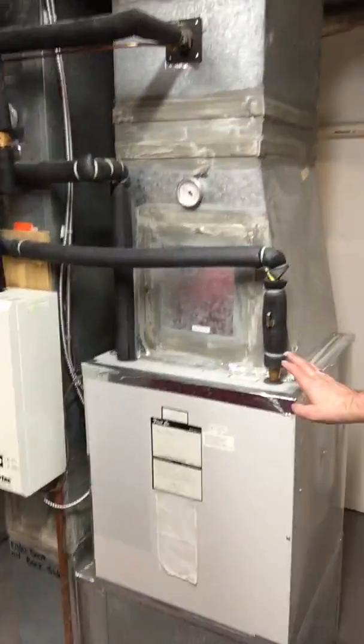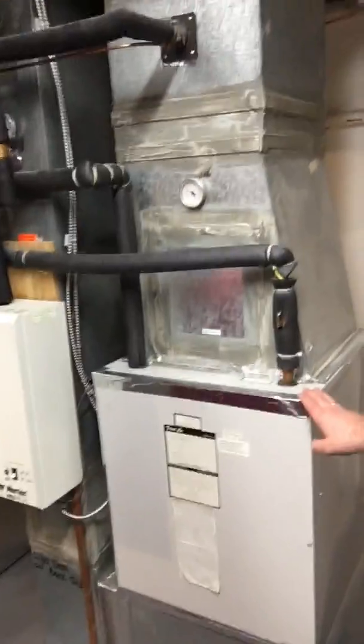So all right, so far we've talked about the snow melt, the pool heating, the radiant, the brains, the control system for that. So now I want to talk about the air handlers. I said it was a hybrid, so we do have the hydronic, but listen, if you want to do air filtration, if you want to do humidification, if you want a good place for secondary heat, fan coils are awesome. So what we have here is our first fan coil. We have two of them, actually three of them, one out in the garage. This one is for the east side of the house, and it does two things.